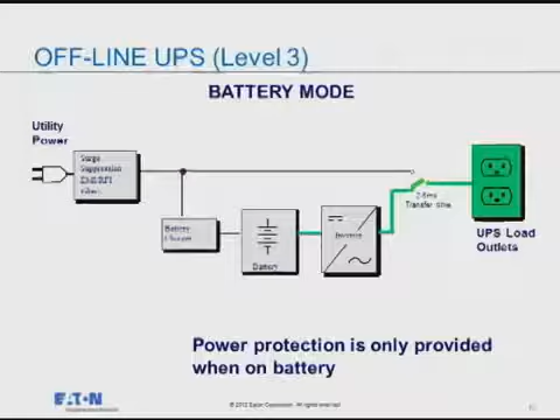Now, if I have a power outage or one of the incidents, it's going to switch to the UPS, and now I've got a battery feeding an inverter, taking that DC and re-inverting it back to AC, giving me power to the load. And typically there's a 2 to 6 millisecond transfer time. But now I've got clean, filtered, regulated power for 5, 10, 15 minutes, depending upon the battery bank.